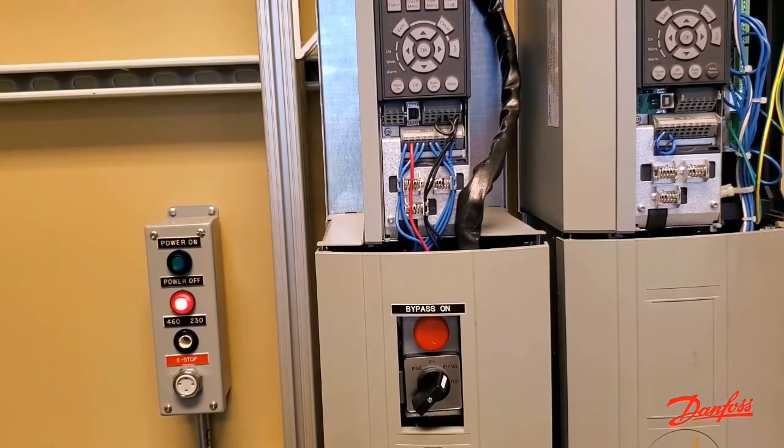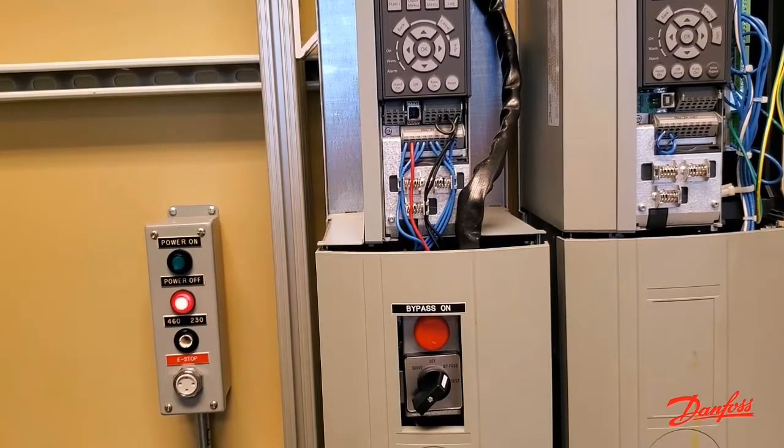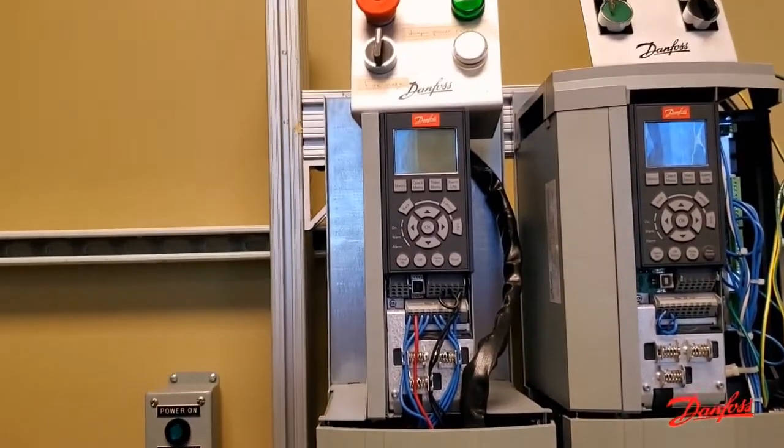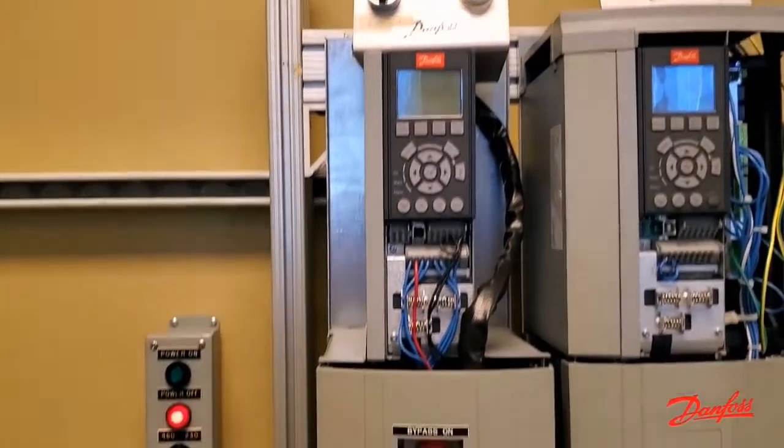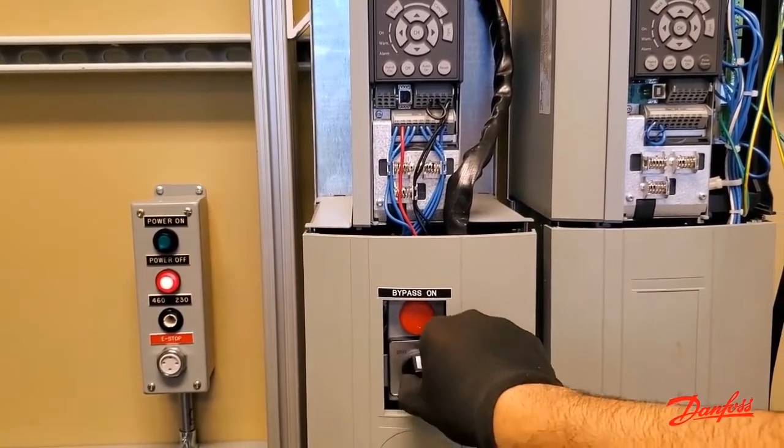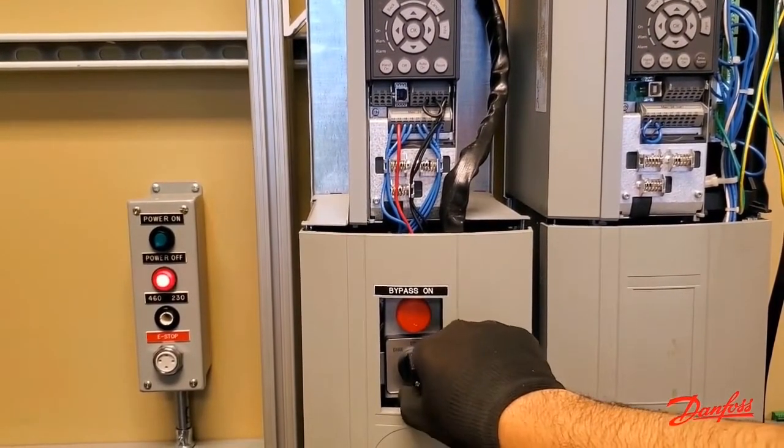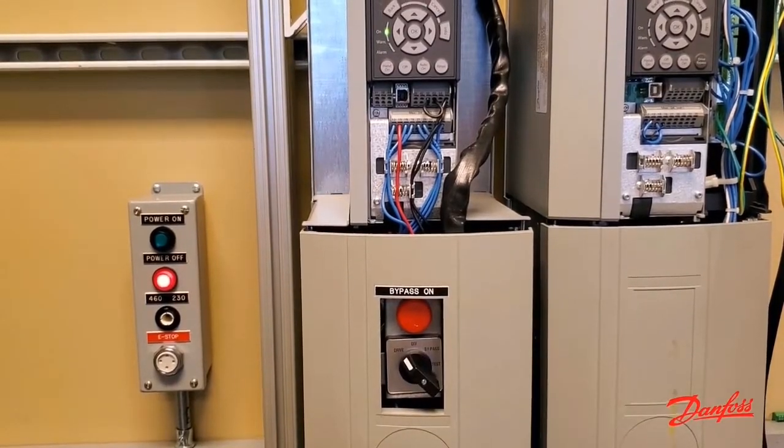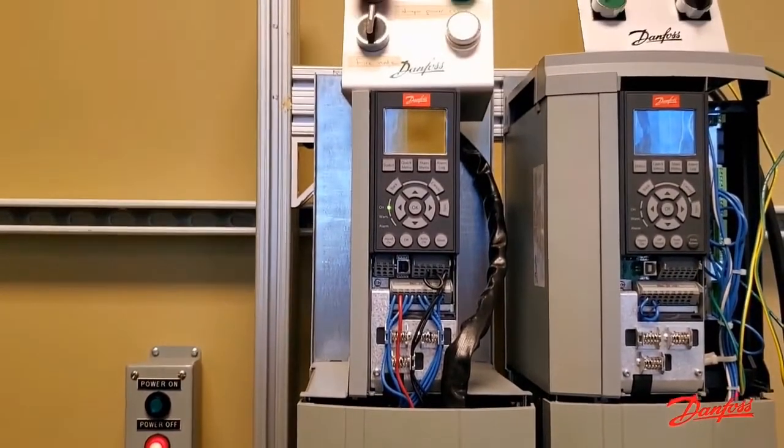Make sure that it's not set to off, and that it has been set to operate in either drive or bypass, allowing it to engage the contactors within the panel, which in turn power up the drive or close the bypass contactor. It's important not to confuse this switch with the mains disconnect, which should also be checked at this stage.